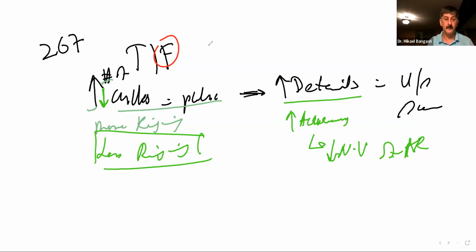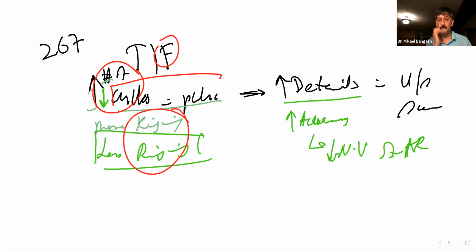So please remember, guys, that the number of cycles per pulse is what we refer to as ringing. More ringing, more cycles; less ringing, fewer cycles per pulse. Did that make sense? Yes. Good.